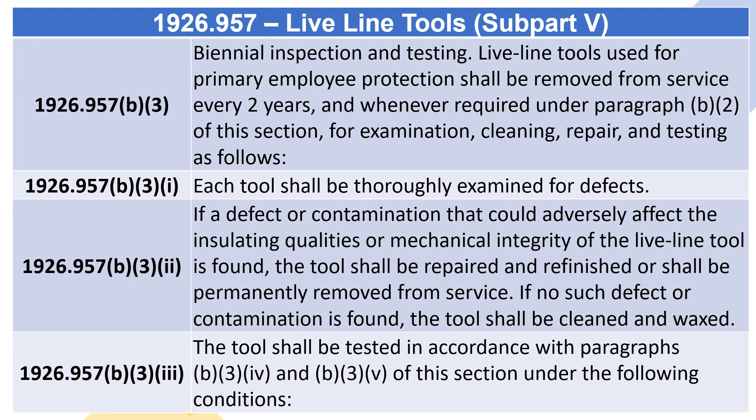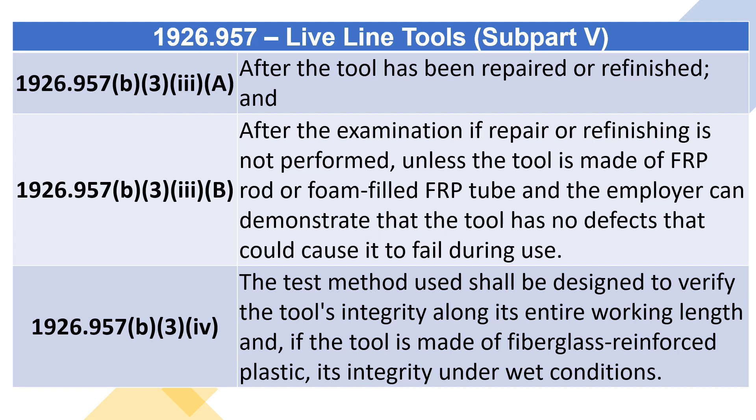The tool shall be tested in accordance with Paragraphs (b)(3)(iv) and (b)(3)(v) of this section under the following conditions: 1926.957(b)(3)(iii)(A) after the tool has been repaired or re-finished, and 1926.957(b)(3)(iii)(B) after the examination if repair or re-finishing is not performed, unless the tool is made of FRP rod or foam-filled FRP tube and the employer can demonstrate that the tool has no defects that could cause it to fail during use.